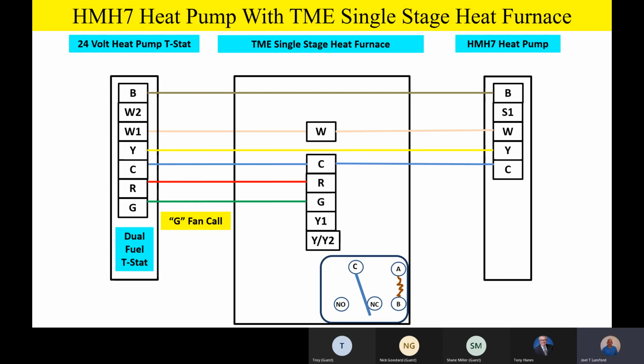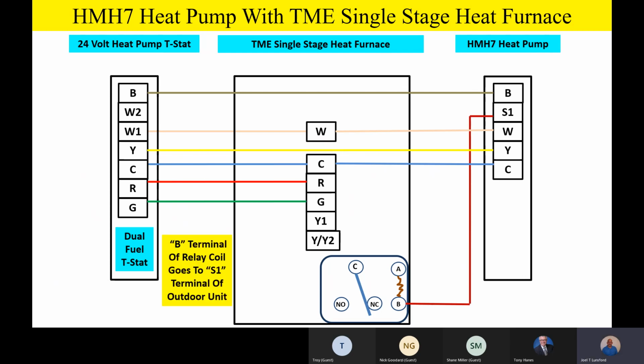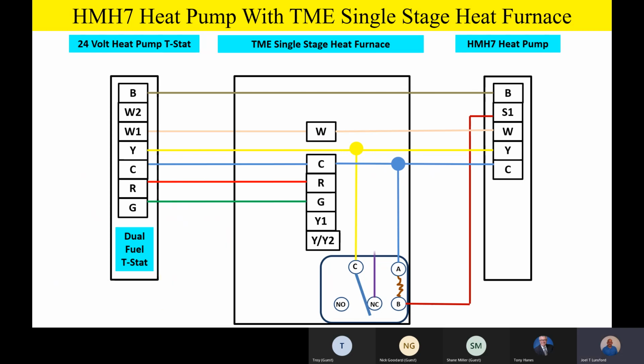Now, as we hook that relay up, remember, team, we're going to be going from one side of the relay up to S1 so we can have that airflow reduction. So we go up to S1 on one side of the relay coil. The other side of the relay coil is going to hook to 24-volt common, so that'll complete the circuit for the relay coil itself. And just like we had before, the common terminal of the switching contacts is going to go up to Y terminal. So basically, anytime we call for cooling operation, or more specifically, anytime we call for compressor operation, we'll have voltage right there on the common terminal for the switching contacts. The normally closed contact on the relay will then go up to Y/Y2. That's going to be our high.